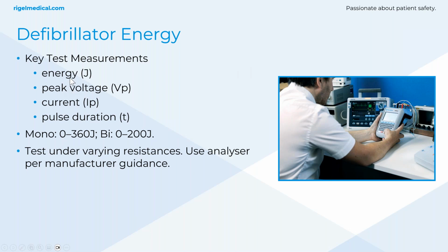Sometimes you have to test for varying patient body impedance. Typically, a manufacturer is only going to specify 50 ohms. That's the standard that's included in most, but the resistance across the body can vary depending on whether it's a larger adult or a small child. So OEMs will typically test across a variety of defibrillator loads just to make sure that there's correct energy output across those loads.